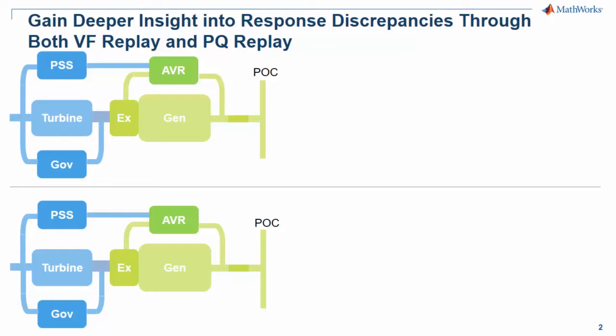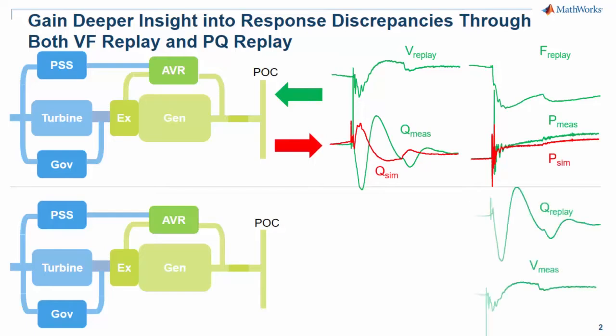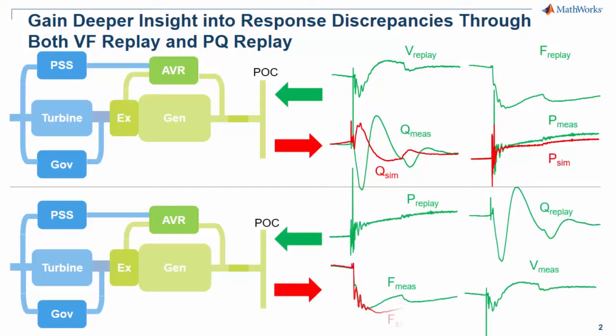Two data replay paradigms are available with these four measurements. First, replay voltage and frequency and then compare simulated active and reactive power with measured active and reactive power. Second, replay active and reactive power and then compare simulated voltage and frequency with measured voltage and frequency.